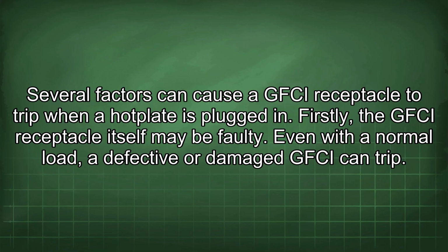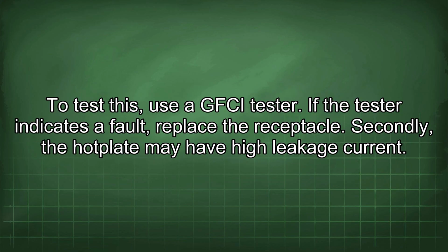Firstly, the GFCI receptacle itself may be faulty. Even with a normal load, a defective or damaged GFCI can trip. To test this, use a GFCI tester. If the tester indicates a fault, replace the receptacle.